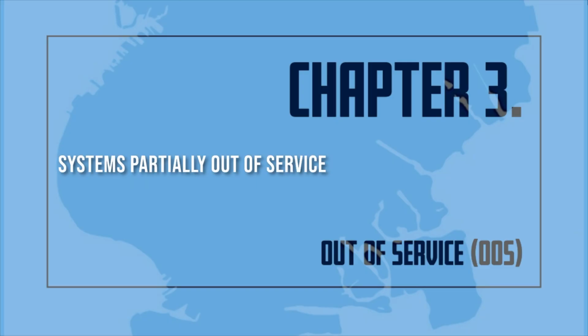Systems partially out of service. The impairment coordinator/building owner shall ensure that the local administrative fire company, a fire suppression piping contractor, fire department units, or a master fire suppression contractor Class A or B has placed one blue disc 8 to 9 inches in diameter on all affected fire department connections. A red tag shall be placed at the main control valve and any closed sectional valve indicating the company name, date of removal from service, and the anticipated return to service date.